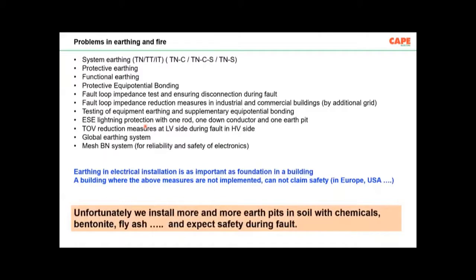And unfortunately, what do we do with respect to earthing? Unfortunately, we install more and more earth pits in soil with chemicals, bentonite, fly ash, and expect safety during fault. So actually, the subject of earthing has nothing to do with the earth pit in soil. Earthing is a subject which is ensuring all these bullet points which I have put here: system earthing, protective earthing, functional earthing, and finally mesh BN. So this is how earthing must be carried out.